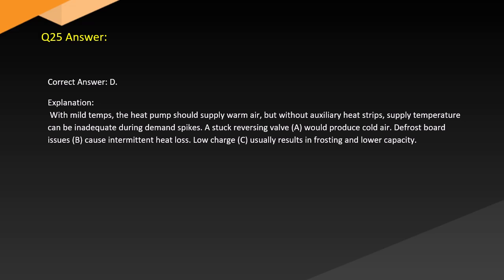Answer. Correct answer: D. Explanation. With mild temps, the heat pump should supply warm air, but without auxiliary heat strips, supply temperature can be inadequate during demand spikes. A stuck reversing valve, A, would produce cold air. Defrost board issues, B, cause intermittent heat loss. Low charge, C, usually results in frosting and lower capacity.